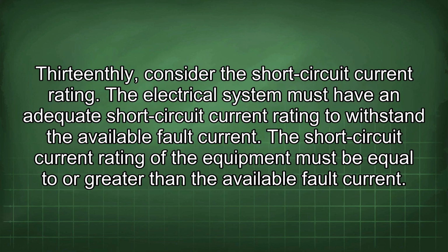13thly, consider the short circuit current rating. The electrical system must have an adequate short circuit current rating to withstand the available fault current. The short circuit current rating of the equipment must be equal to or greater than the available fault current.